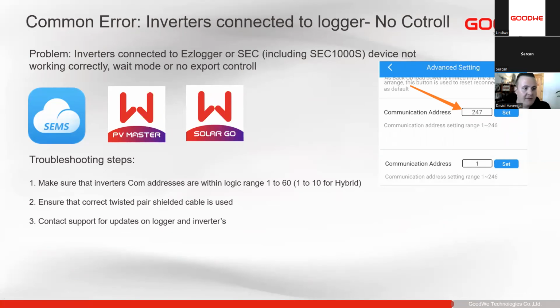So next we have if the inverter is connected to a logger but is not controlling. So similar to the remote disconnect, very often our inverters can then remain in a wait mode, especially the on-grid inverters will then sit and wait in a wait mode. We always need to make sure to configure our inverters.